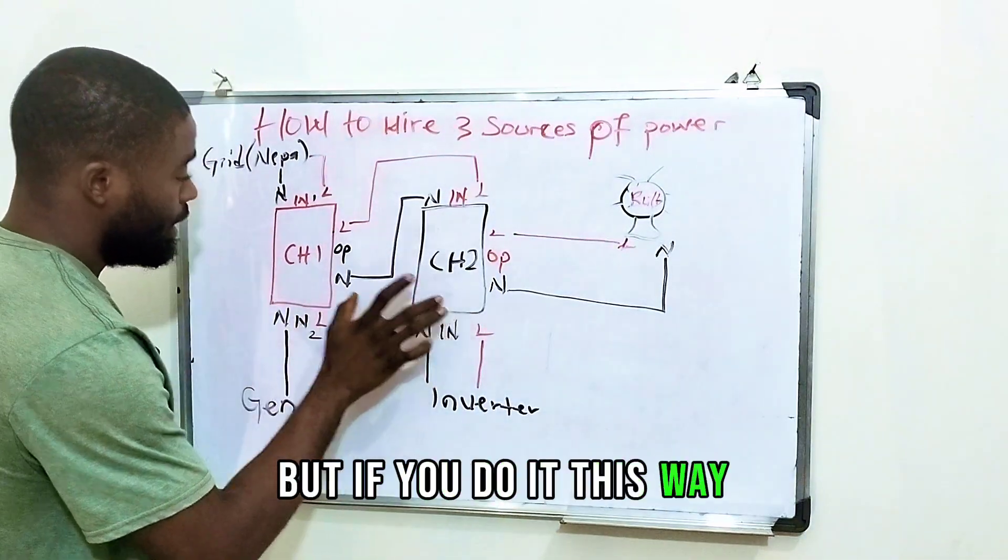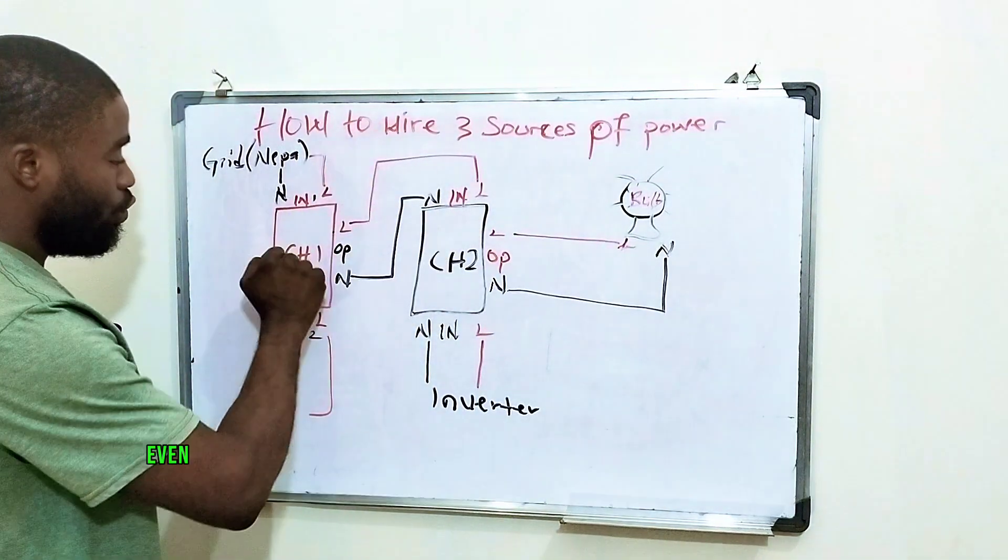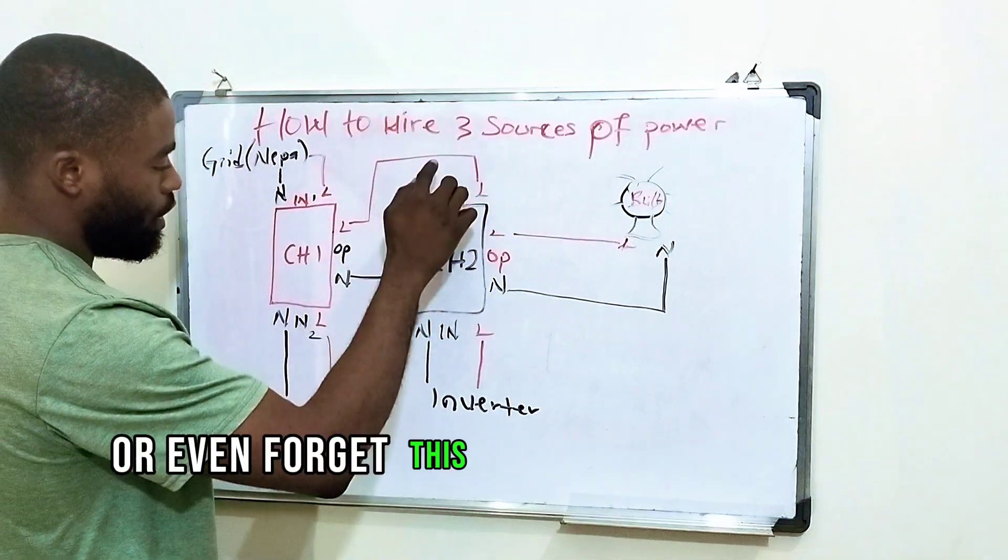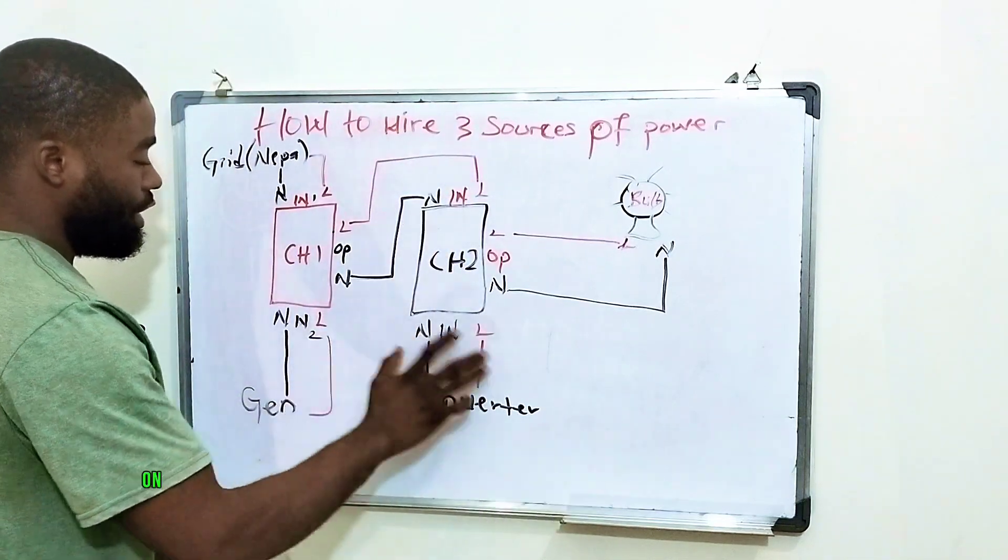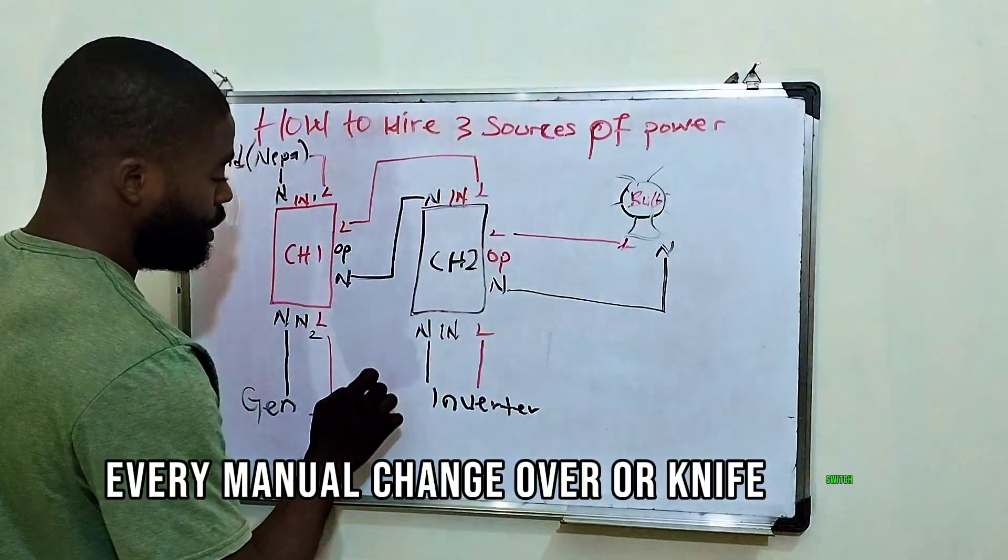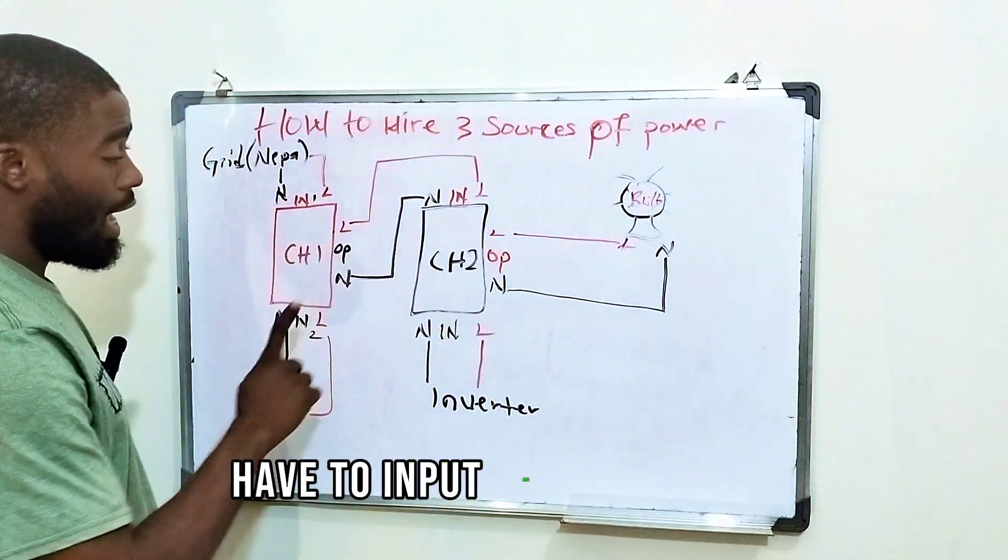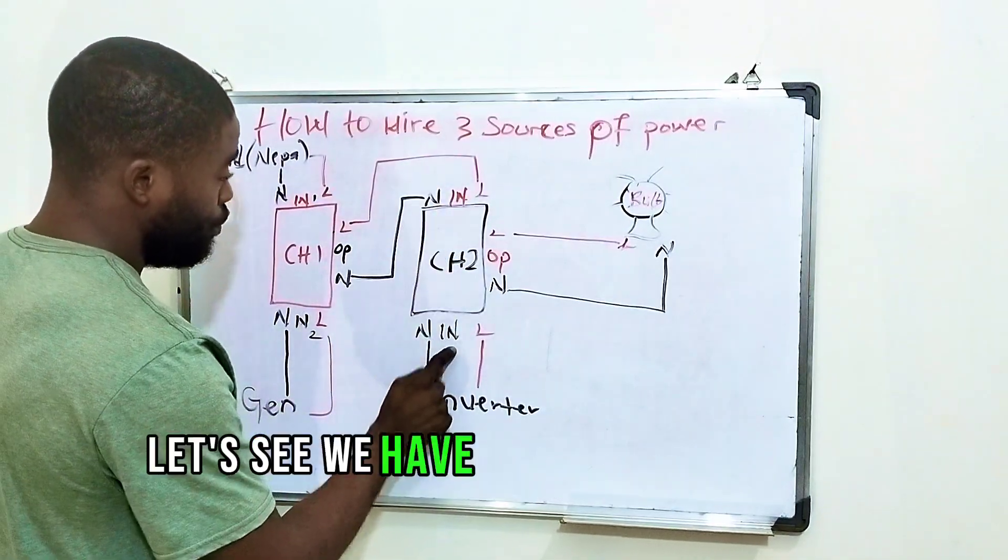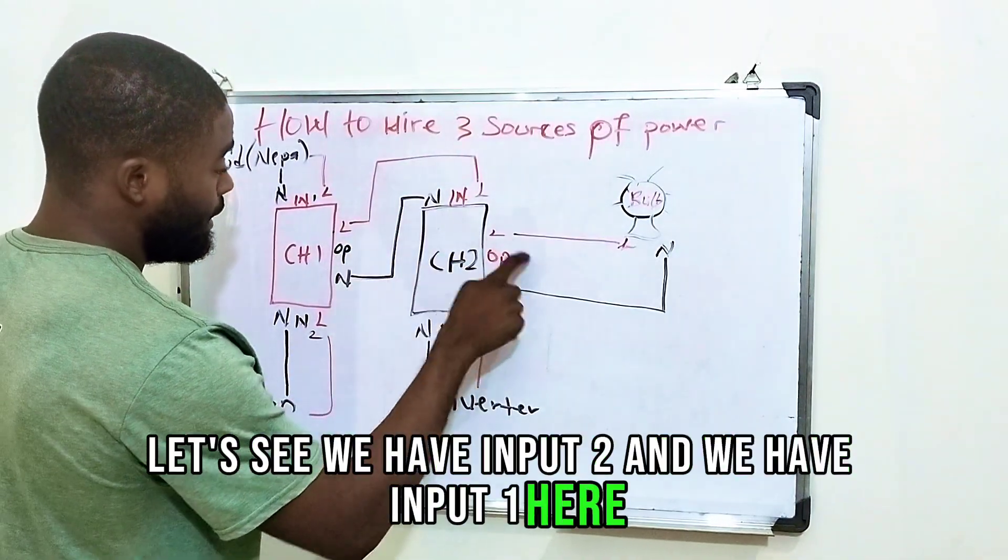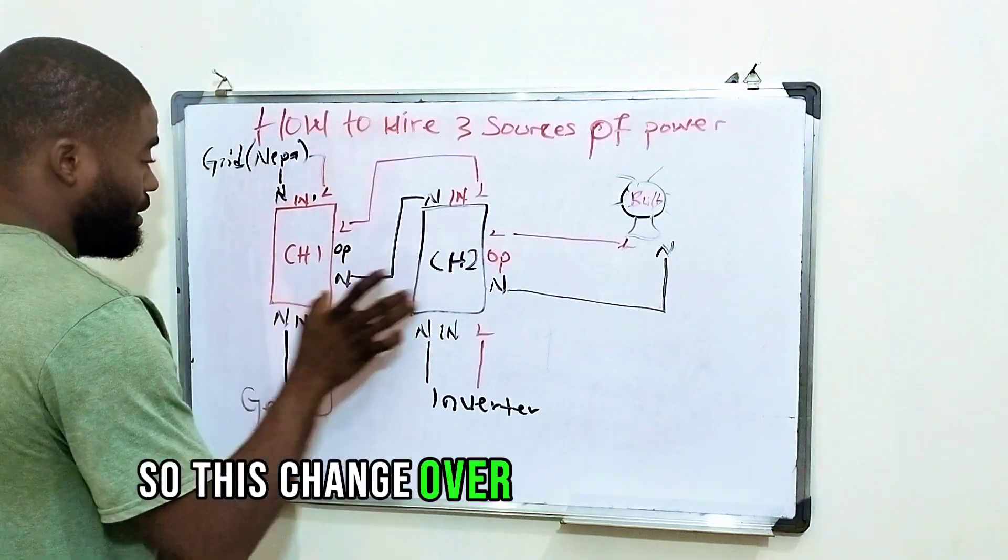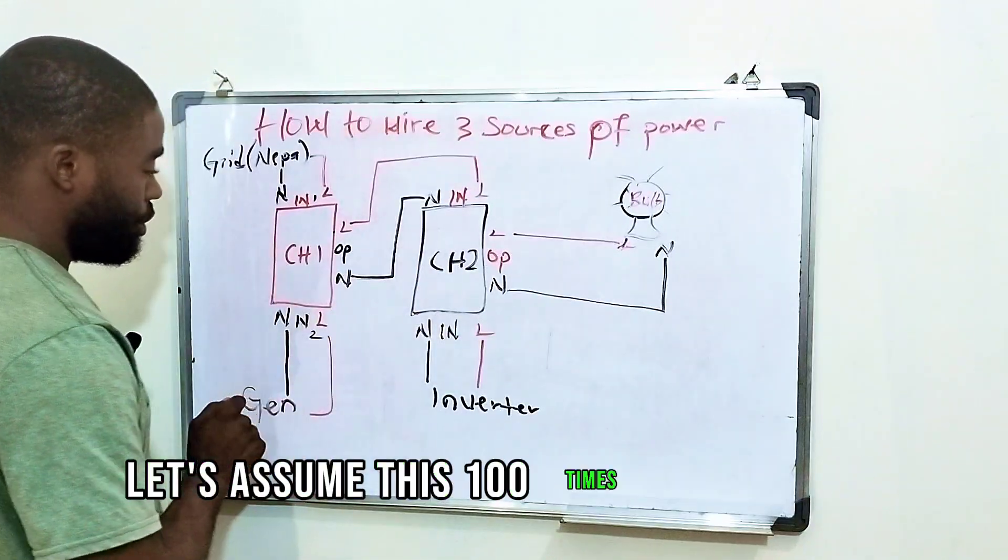But if you do it this way, there will never be collision of light even when you forget your changeover down or you forget this one up, or forget this one down on any of these three sources of light. Every manual changeover or knife switch has two inputs and one output. So we have input two and we have input one here. Then we have one output. We have another changeover here.